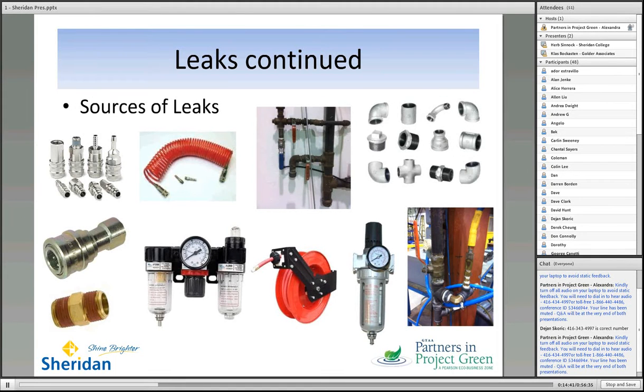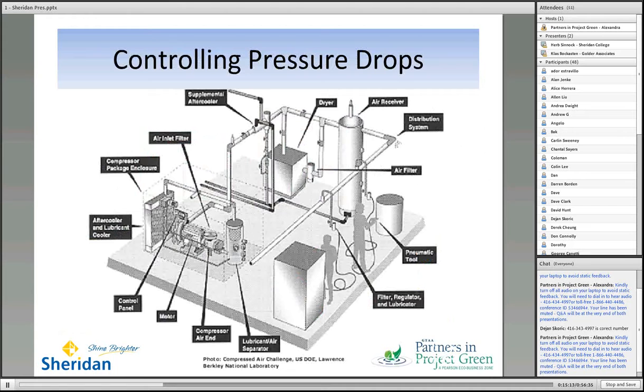And then another one that's kind of surprising, which is the little solenoid-operated drains at the bottom of receiver tanks. I was in a plant last week that was wonderfully managed. It looked like they were really paying attention to the compressed air system. It had a few issues, but we walked into the compressor room and straight away you could hear hissing. I walked right over to the receiver tank, and sure enough, the drain solenoid was wide open, stuck open, and we were bleeding air off the system. It happens. You've got to pay attention to it.